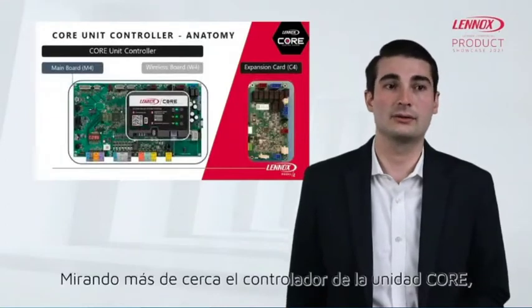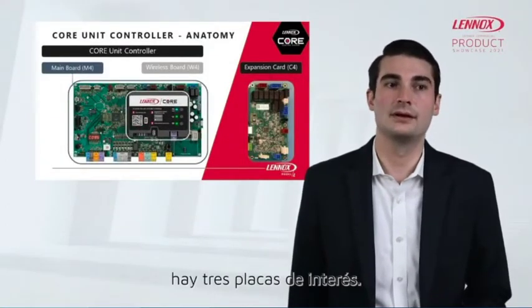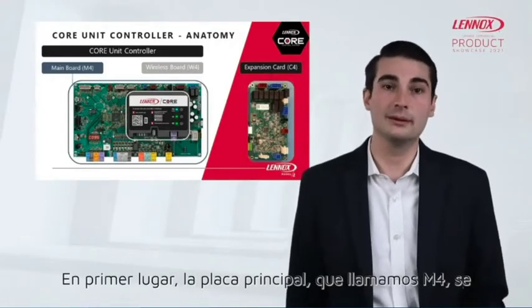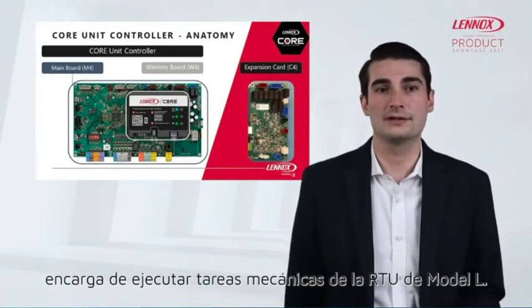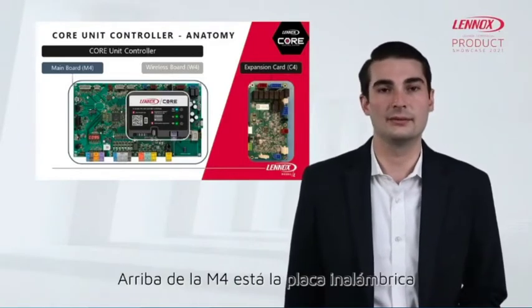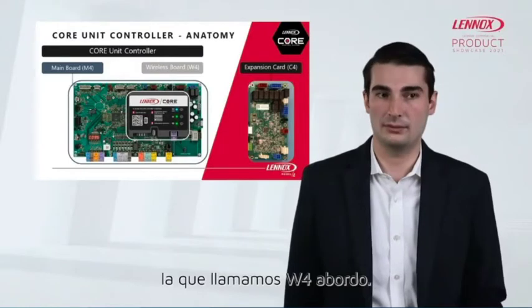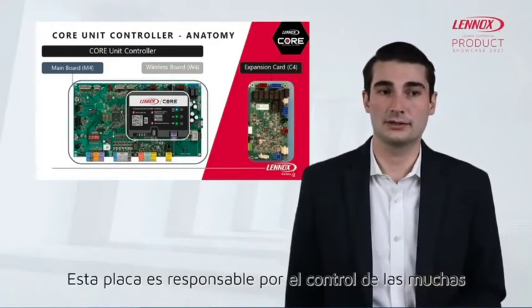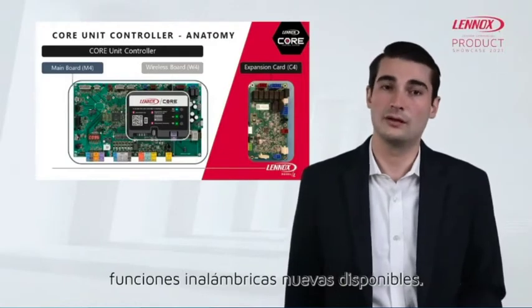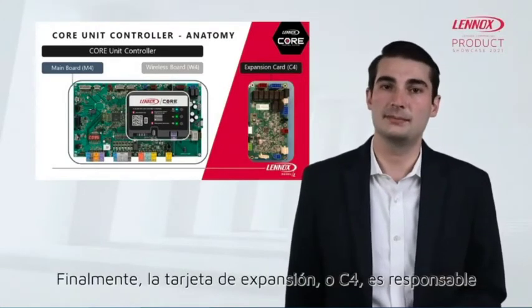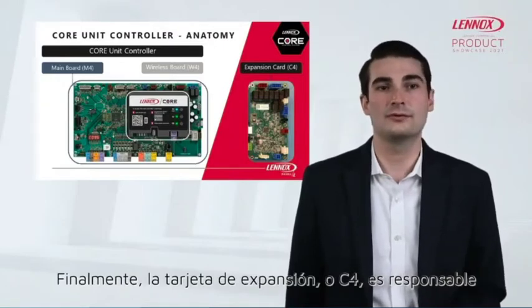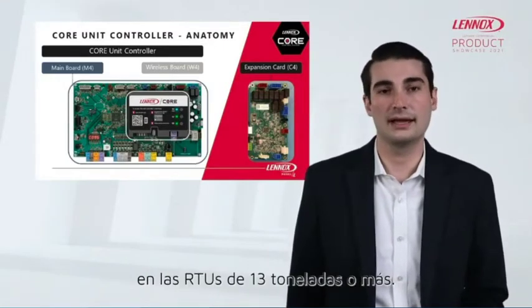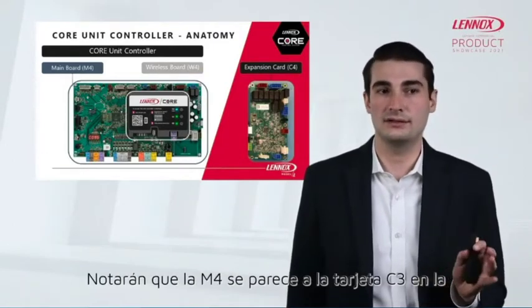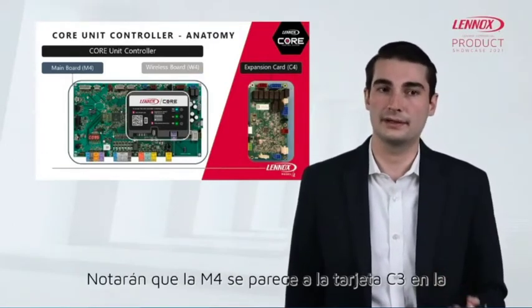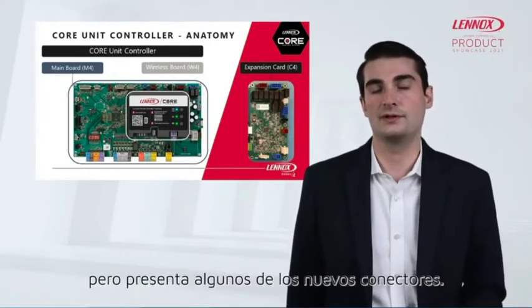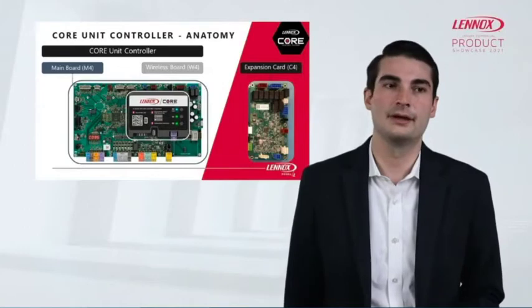Looking closer at the Core Unit Controller, there are three boards of interest. First of all, the main board, what we call the M4, is responsible for running the mechanical parts of the Model L RTU. On top of the M4 is the wireless board, or what we call the W4 board. This board is responsible for control of the many new wireless functionalities available on this RTU. Finally, the expansion card, or C4, is responsible for running the extra mechanical equipment on the 13-ton and larger RTUs. You'll notice that the C4 card closely resembles the C3 card on the current controls platform with Prodigy 2.0, but features some of the new connectors.